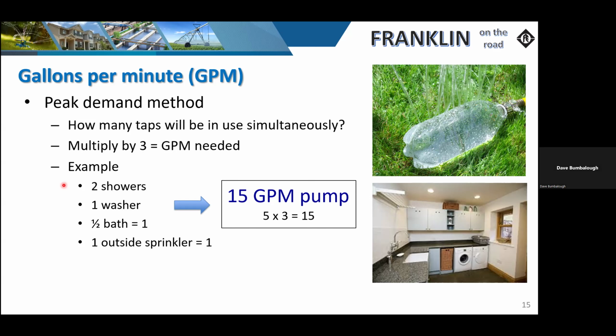And those are questions that we need to ask the building contractor and or see for ourselves when we're making this calculation. So as we go through, I'm just using this as a standard calculation. We're going to see that there's 5 items in there. We're going to multiply by 3, and there's where our 15 gallons per minute comes from.